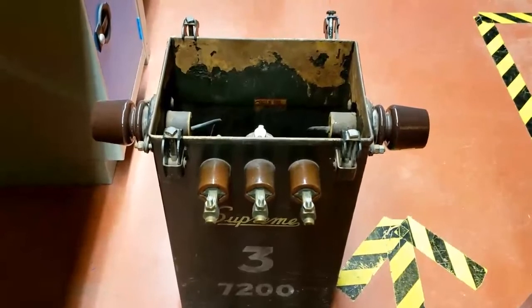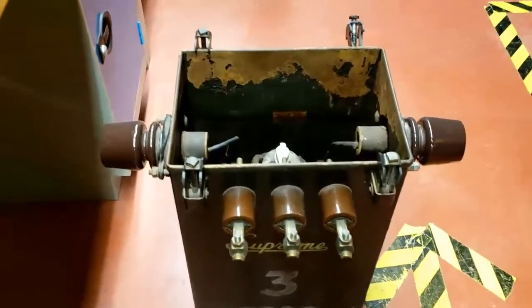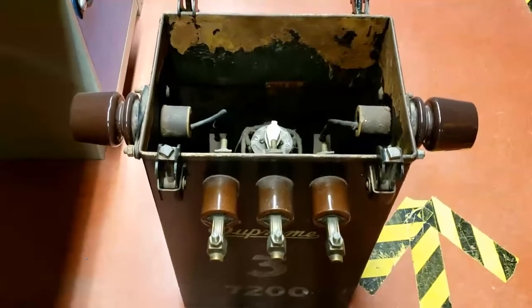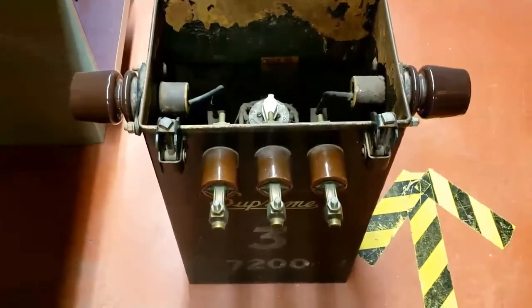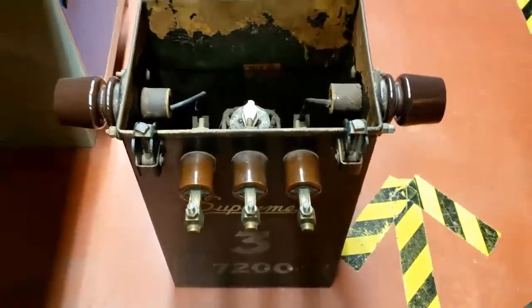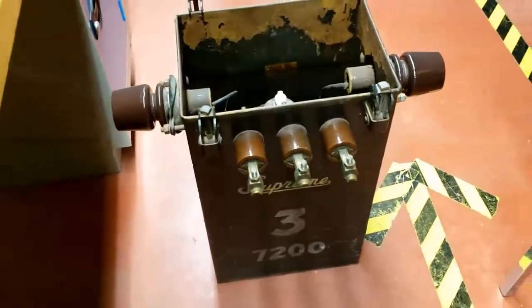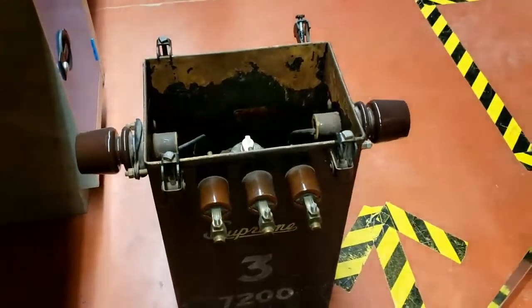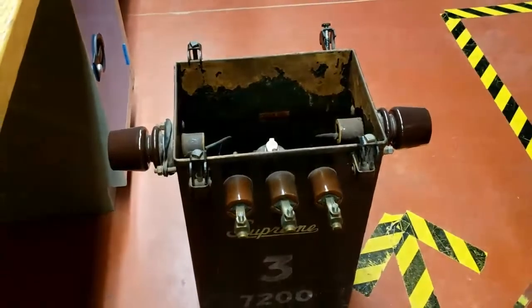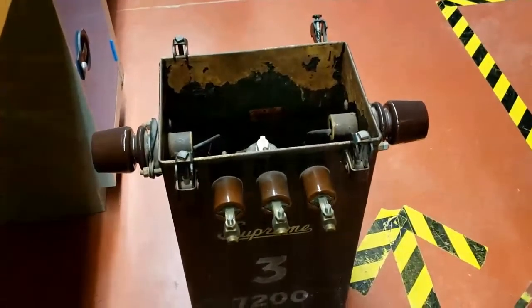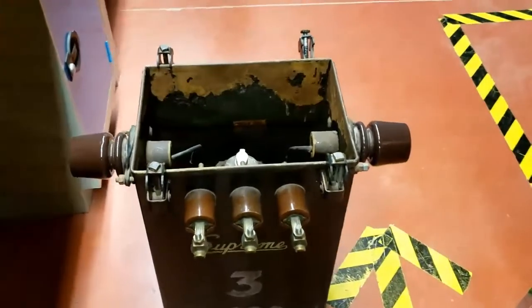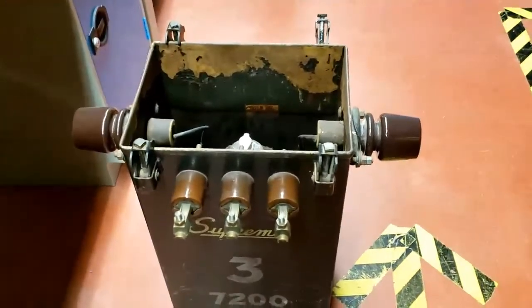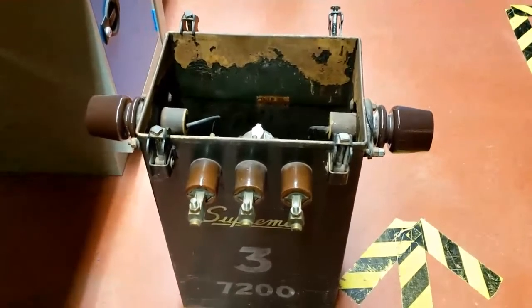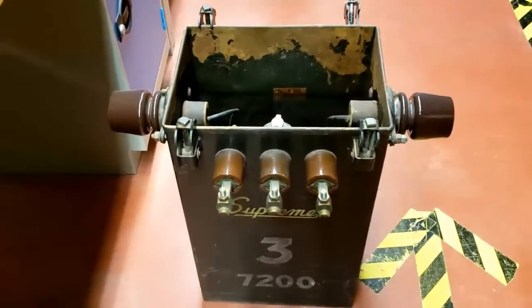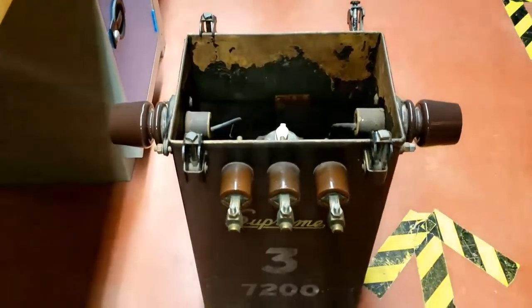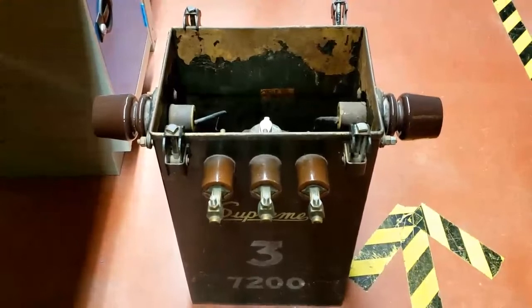So these transformers get old. You want to test the resistance of it. Part of preventative maintenance is recording these values on a regular basis. As long as the values don't change, then the equipment hasn't changed. But as soon as some of your readings start to change, historically you can see that resistance is starting to decrease and decrease. Or in the case of other devices, maybe it's increasing, maybe the current is increasing. Then you know that there's some maintenance required. So you can catch something before it blows up and fails utterly.